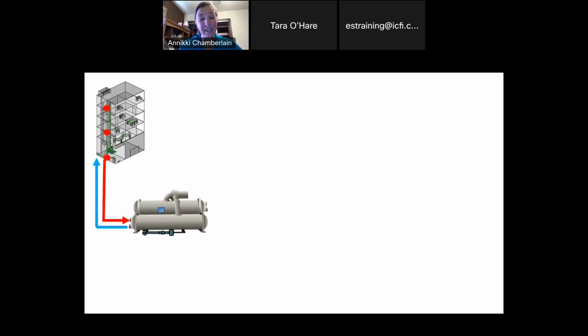So the way cooling towers work, we have a process of some kind. It could be a building, it could be a refrigeration system, something that is generating heat. We want to get that heat out of there so that we have that nice, lovely coolness that we like for comfort or food products or whatever it may be. So we're going to remove that heat out of the building. Typically, we're sending it to some kind of chiller. I would love to deep dive chillers today, but we've got a lot to talk about, so we're not going to. But there is magic that happens inside of that chiller. Basically, we get rid of that heat and send our water back to the building, cool and ready to pick up more heat. So that's a loop that's always going.